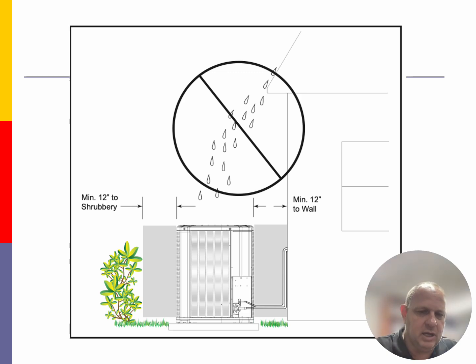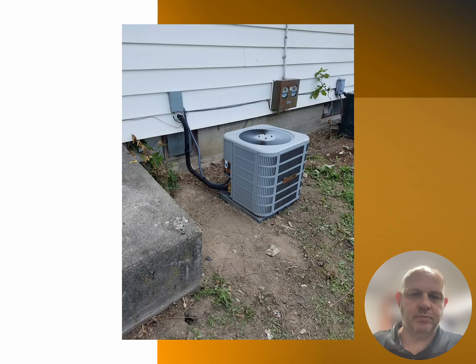Now here's a nice install, nice clearance around the actual unit itself. Line set is ran nice and tight against the wall, and then out to the outdoor unit. Good airflow coming around it. Disconnect whip is ran along with it. I'd like to see that guy a little tighter, looking at it in the picture this way, but for the most part, a decent install for this condensing unit that we're going to be running.